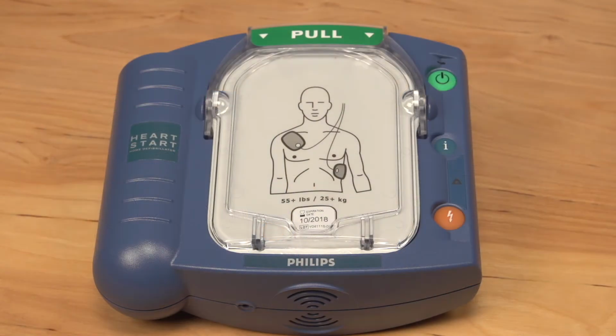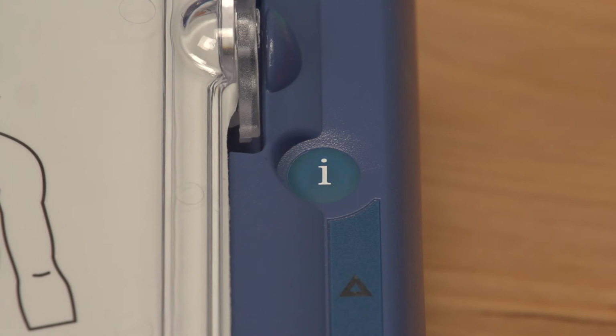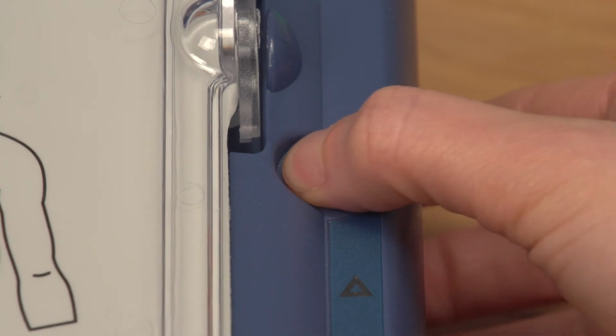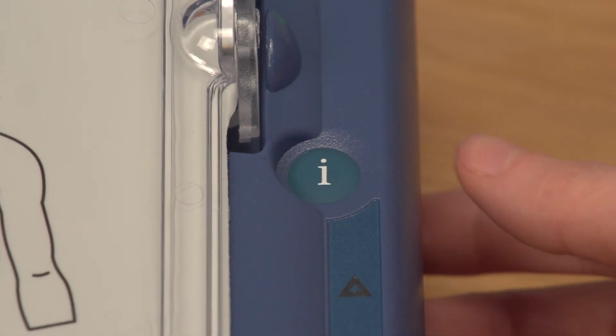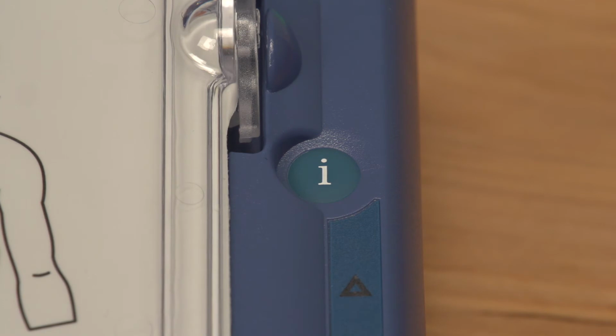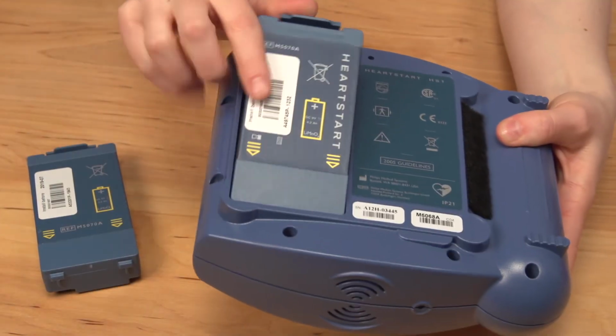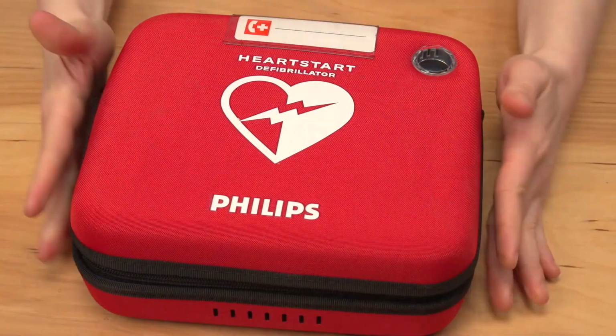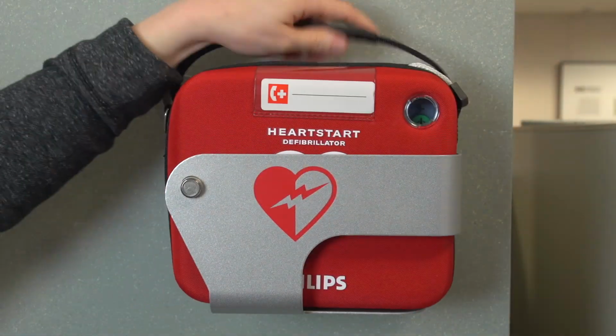A single chirp indicates that the defibrillator requires routine maintenance, such as replacement of pads or installation of a new battery. Press the flashing blue I button to hear additional information about the cause of the single chirp. "Low battery. Insert fresh battery." Perform the necessary maintenance to resolve this issue and return the defibrillator back into service.